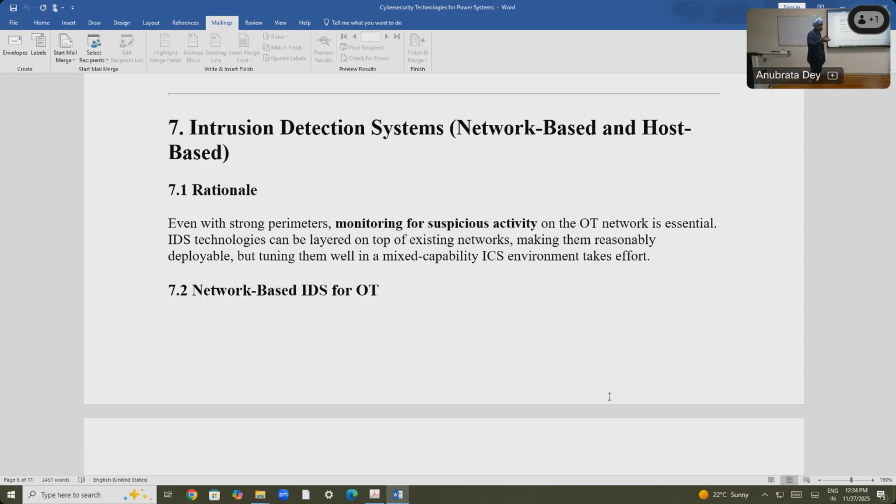So, that's one simple rule that you could set up. And usually when they monitor the traffic, majority of the time on your network, you have an idea of the traffic volume, right? Approximately this much volume. Actually, I'm not sure if I will get time, but we did monitor IEC 61850 traffic in a substation. And from that traffic profile, you could use that to define the rules for intrusion detection. You could say, if you suddenly see 15 GOOSE messages, that means something is wrong. Usually that doesn't happen in your substation.